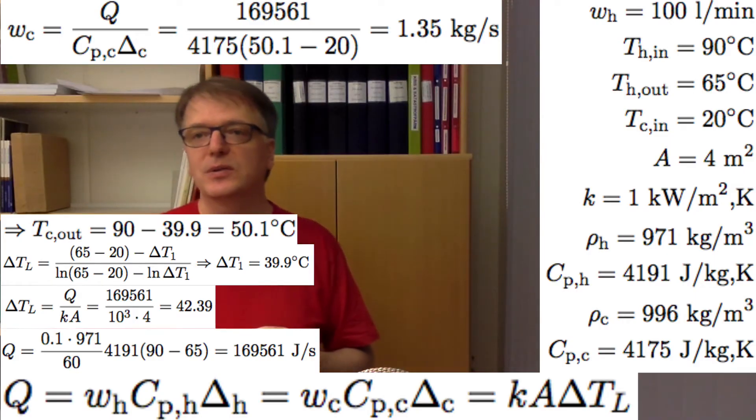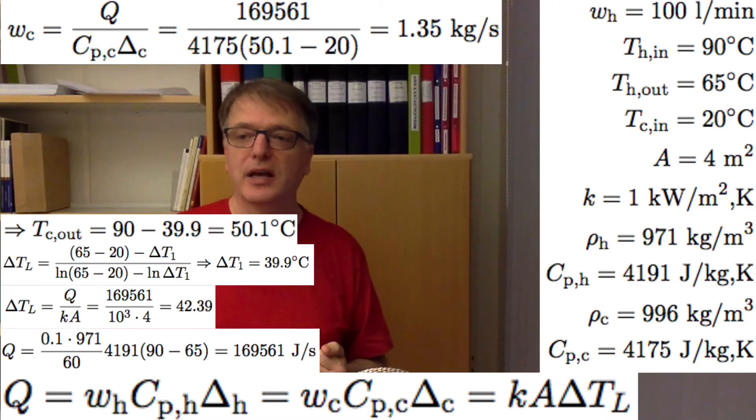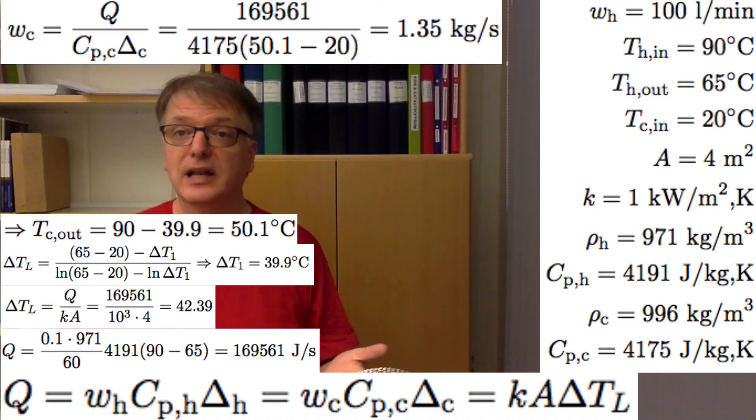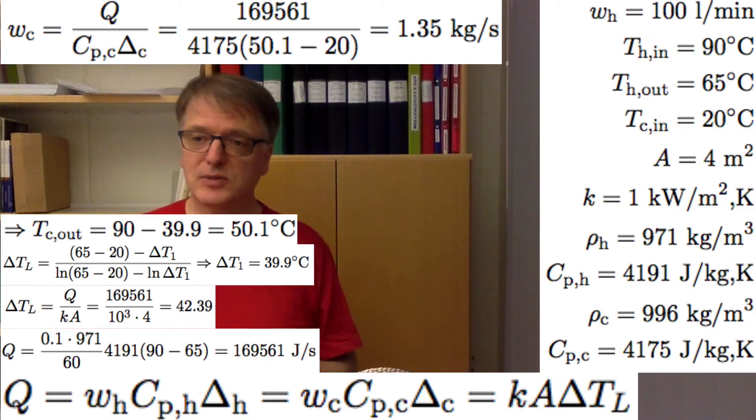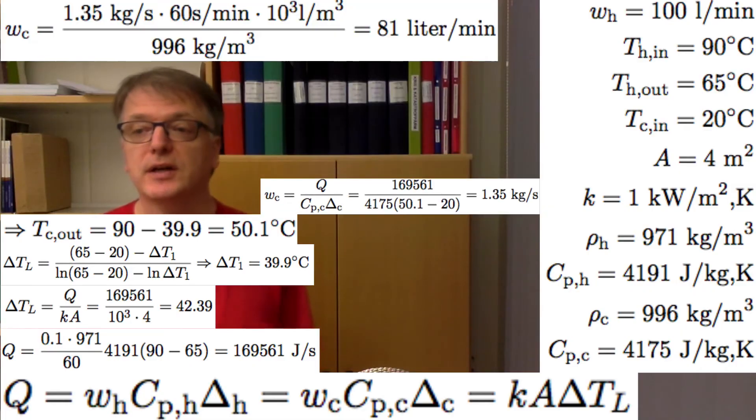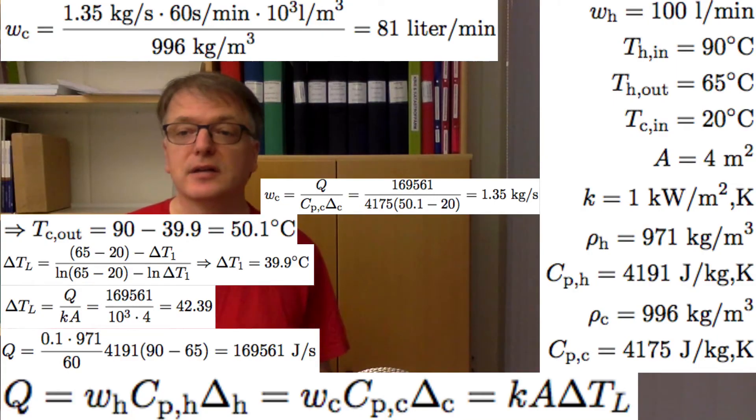So w_c, that must be Q divided by heat capacity and the temperature change, and we get that as 1.35 kg/s, which is less than 1.62, so it seems to be in good order. If we want to we can recalculate that as liters per minute: 1.35 kg/s times 60 seconds divided by the density, and you get 0.081 m³/min or 81 liters per minute.